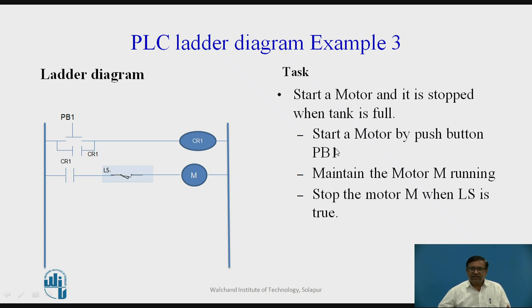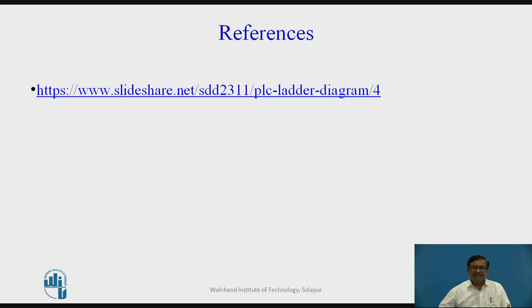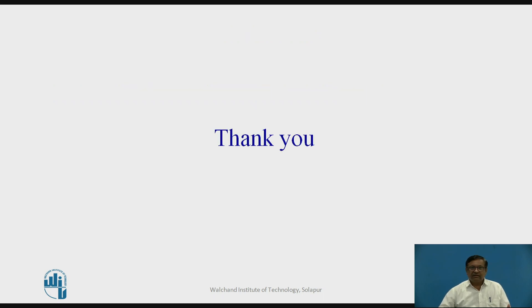To summarize example 3: start the motor by push button PB1, maintain motor M running, and stop motor M when the limit switch LS becomes open — meaning the tank is full. This way we can automatically control the operation of filling a water tank using this ladder diagram. References: this PowerPoint presentation was sourced from the internet for creating the slides.